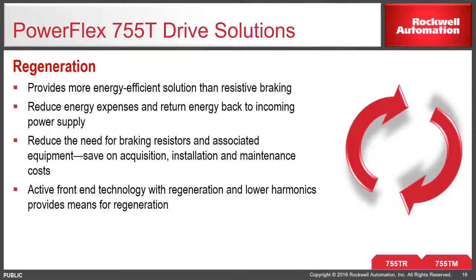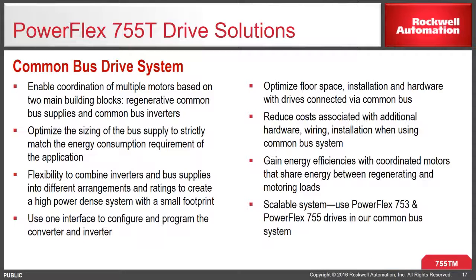The PowerFlex 755TM is our common bus drive system. It enables coordination of multiple motors based on two main building blocks: regenerative common bus supplies and common bus inverters. It optimizes the sizing of the bus supply to strictly match the energy consumption requirement of the whole system. It has the flexibility to combine inverters and bus supplies into different arrangements and ratings to create a high power, dense system with a small footprint.